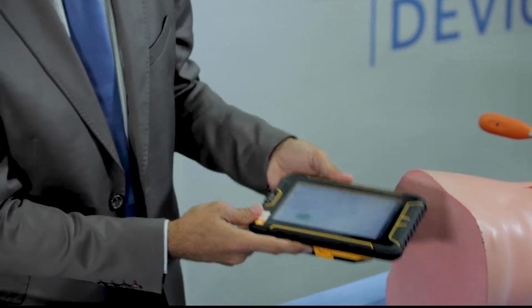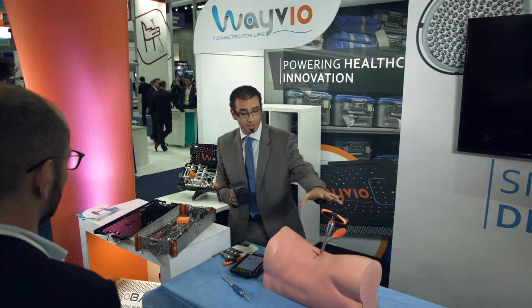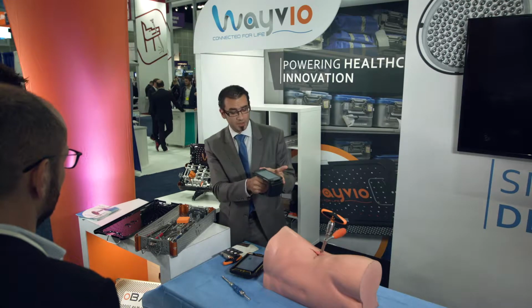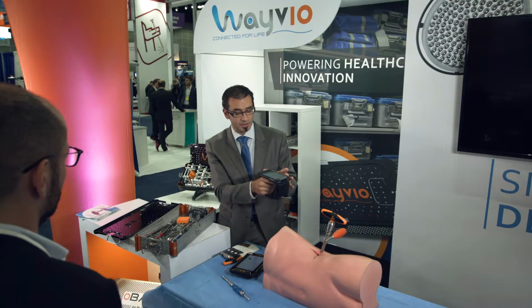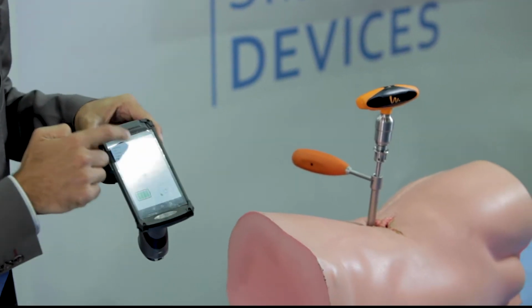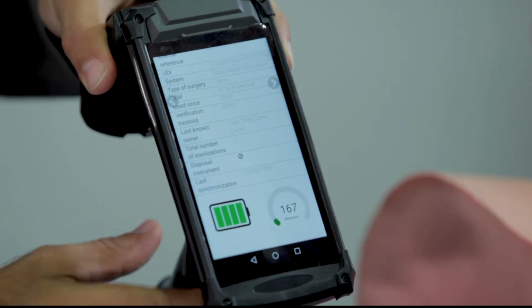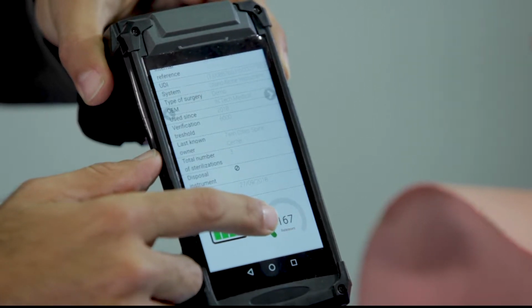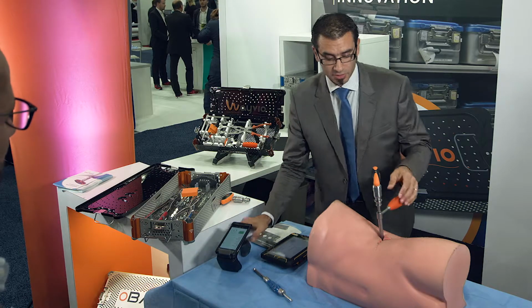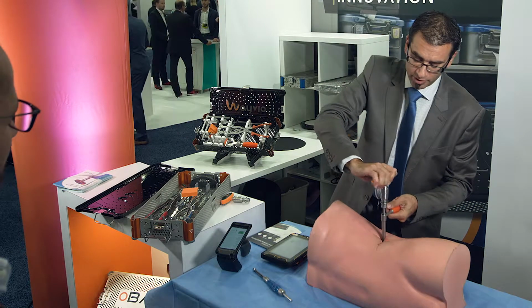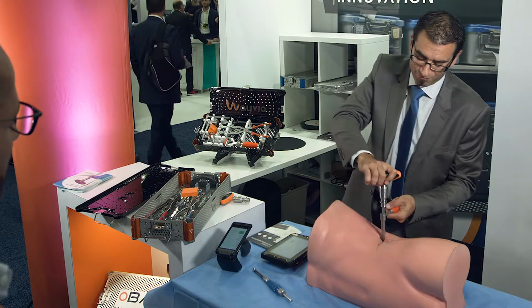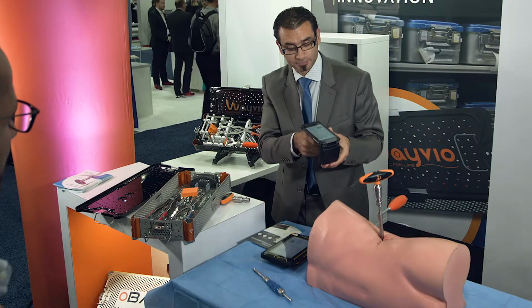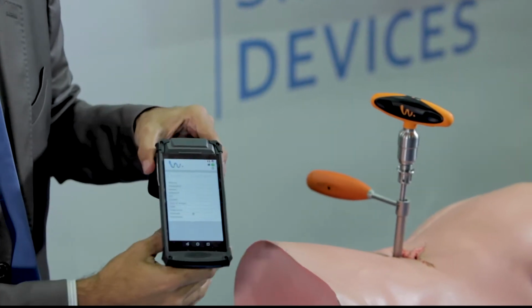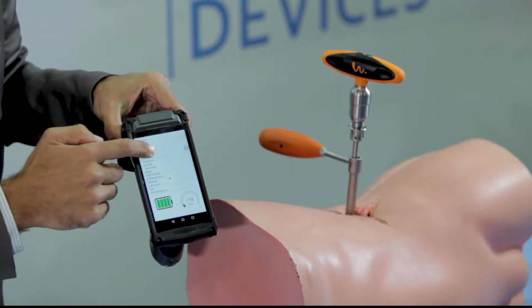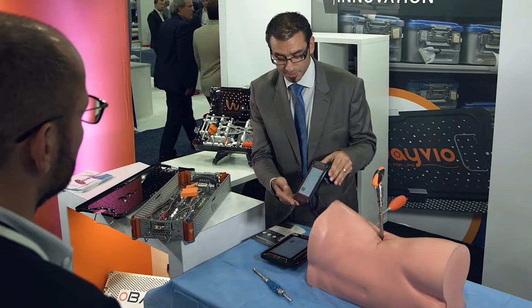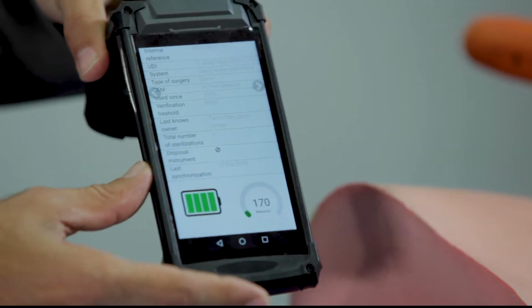So let me show you how this part works. This is the torque limiter in situation. I can just scan this precise instrument. The application will show you that this torque limiter had 167 releases. So if I'm in the operating room and the surgeon releases 3 times, those 3 releases have been counted, and we're now at 170 releases.